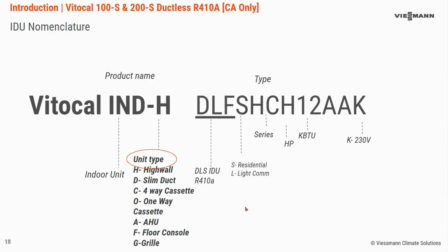The next part of the model number, this is where that DLC comes in. Now we see it's a DLF. So for the indoor unit, it's going to be DLF, outdoor unit DLC. The way I remember it is DLF is a fan coil, ductless fan coil. The next letter is going to let you know if it's a residential or a light commercial indoor unit. The multi-zone, there is no call out for a specific multi-zone indoor unit. As we mentioned, the single zone indoor units are compatible with multi-zone systems, so there's no picking and choosing special indoor units between multi and single zone.